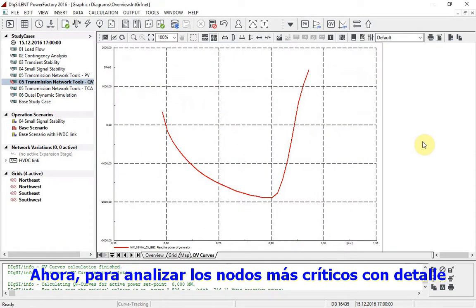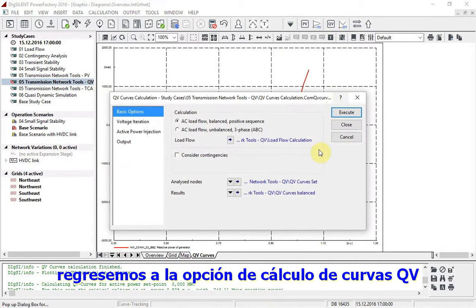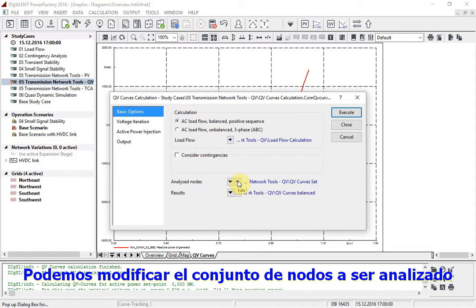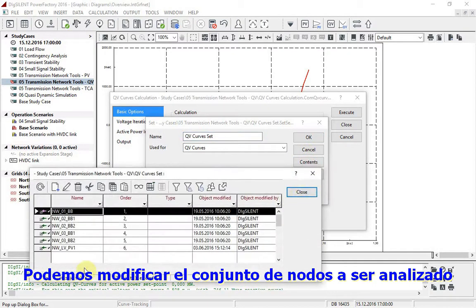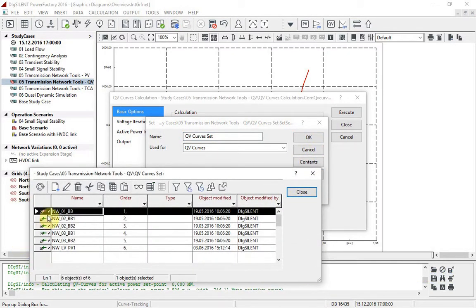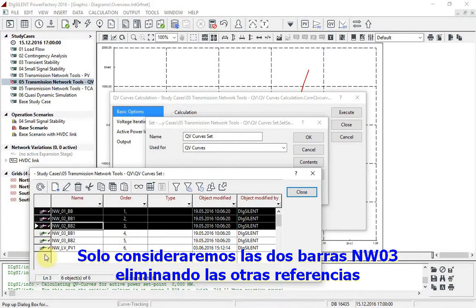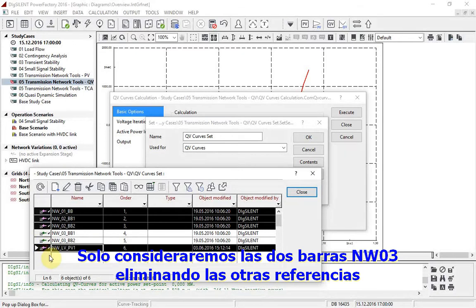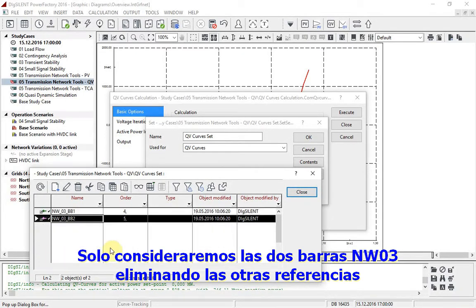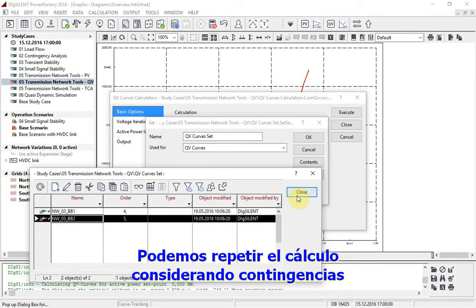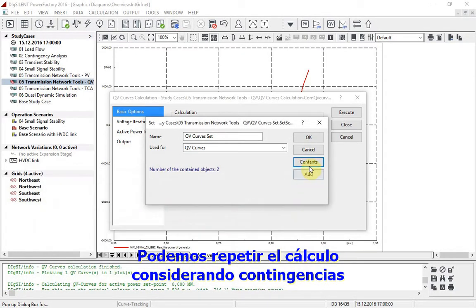Now, in order to analyze the most critical nodes more carefully, we will return to the QV curves calculation option. The set of nodes to be analyzed can be modified. We will consider just the two NW03 busbars by removing the other references. We can now repeat the calculation.